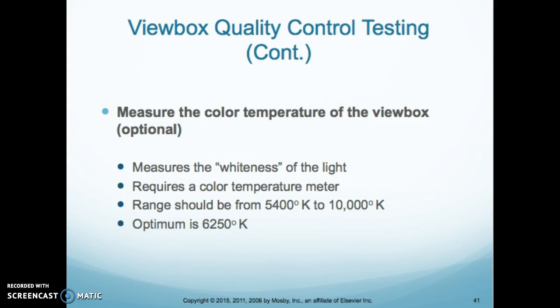We need to make sure that the color temperature of the view box — we look for the whiteness of the light. This requires a color temperature meter and the range should be between 5,400 to 10,000. The optimum is 6,250. When we're looking for color temperature, we look for the whiteness of the light.